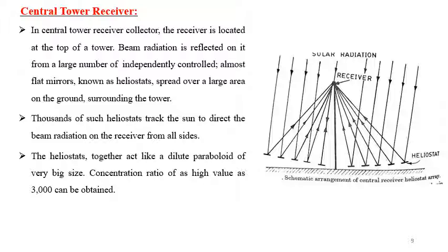The basic problem associated with the central receiver is that the heliostat mirrors require a nonlinear drive rate in two coordinates to achieve the requirement of keeping the reflected image on a point on a fixed receiver. Along with this, the problem is the requirement that the heliostat is rugged enough to survive storms and operate successfully in moderate wind conditions.